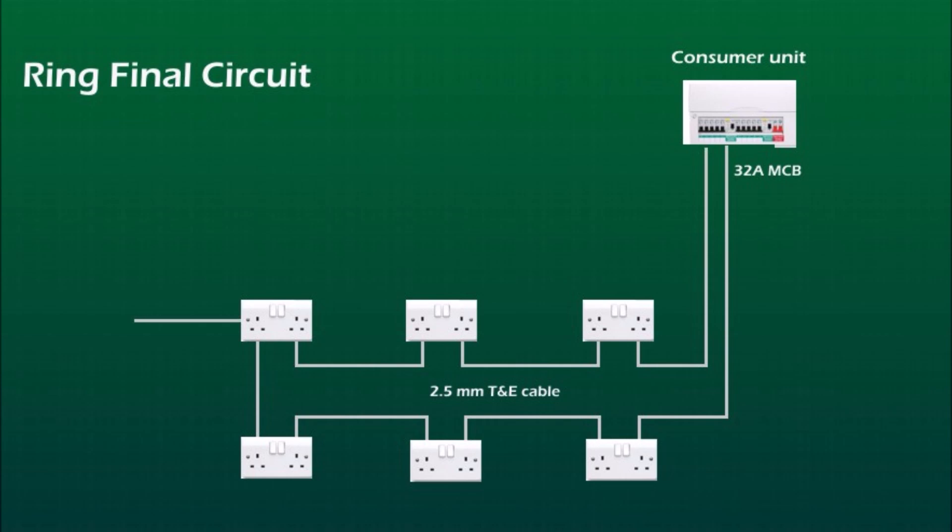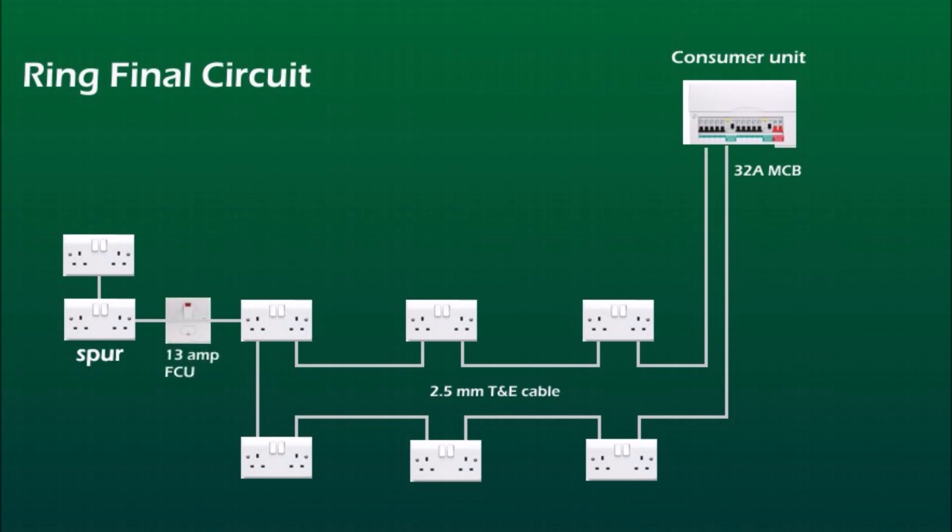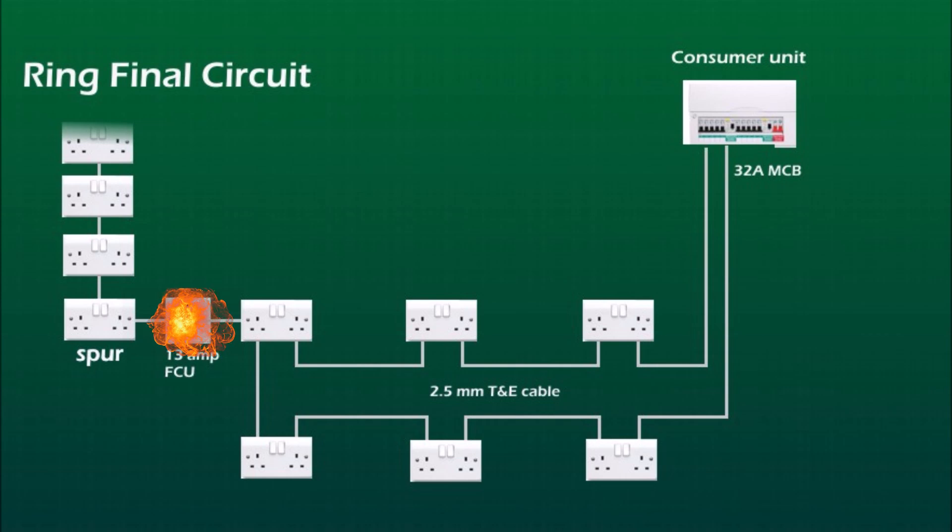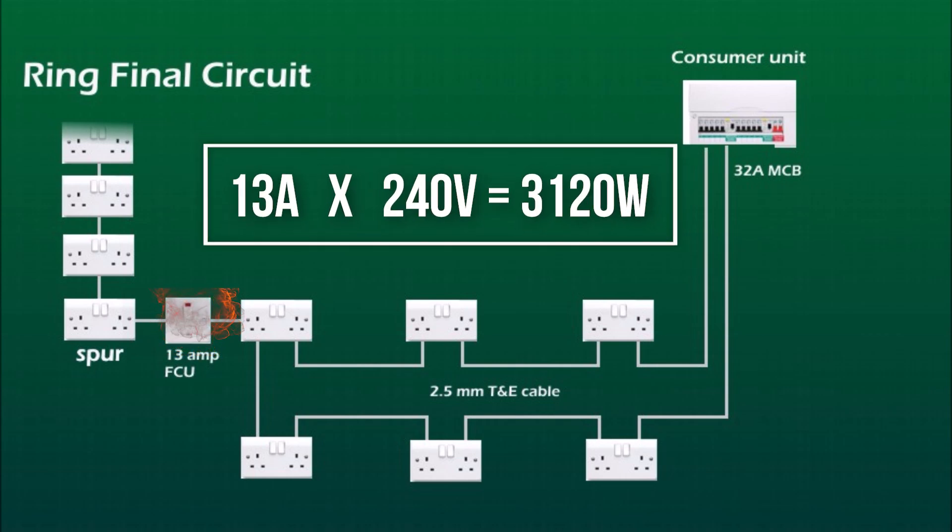If you want to make a spur from any of the socket outlets, simply use 2.5mm twin and earth, run to the spur socket and that's it. If you need more spurs after the first one, then between the ring and the first spur you need to install 13 amp Fused Connection Unit and then you can have unlimited number of socket units on this radial leg of the ring. If you connect too many appliances to this spur socket and they draw too much current, then obviously the 13 amp fuse in FCU will be blown and the fuse is limited to 13 amp. 13 amp by 240 volts that gives us 3,120 watts.